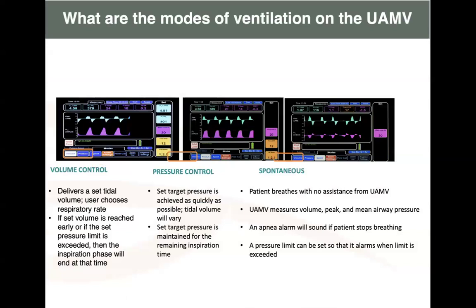These are the different features that you have in the different modes of ventilation. In the volume control, you set your tidal volume, which is a fixed parameter, and then the pressure will be variable. When the pressure exceeds the limit, you get an alarm to show that there's high pressure in the respiratory tract, and then you can adjust any parameter that is needed for you to control the pressure.